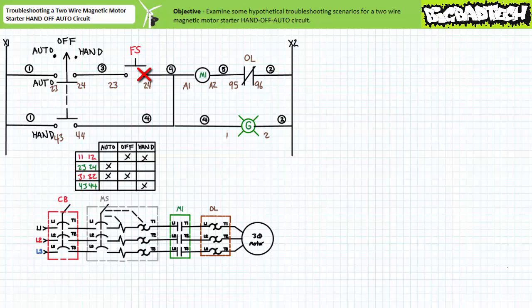When in auto mode, the closure of the float switch will not start the motor. If, however, the selector switch is moved to hand mode, the logic in rung 1 is bypassed and the motor starts.